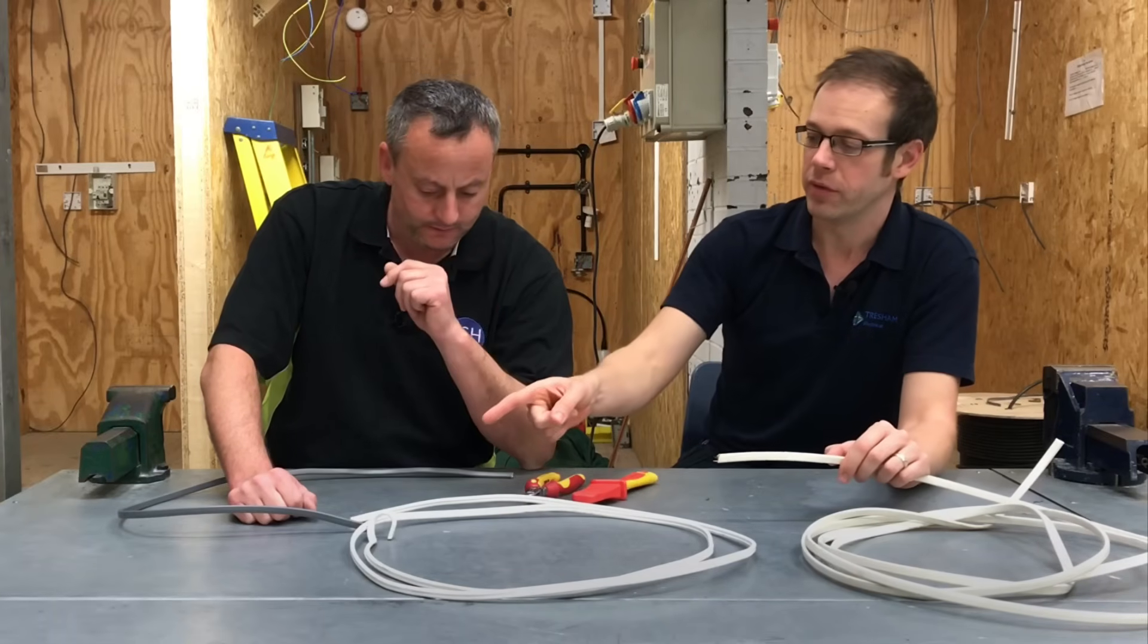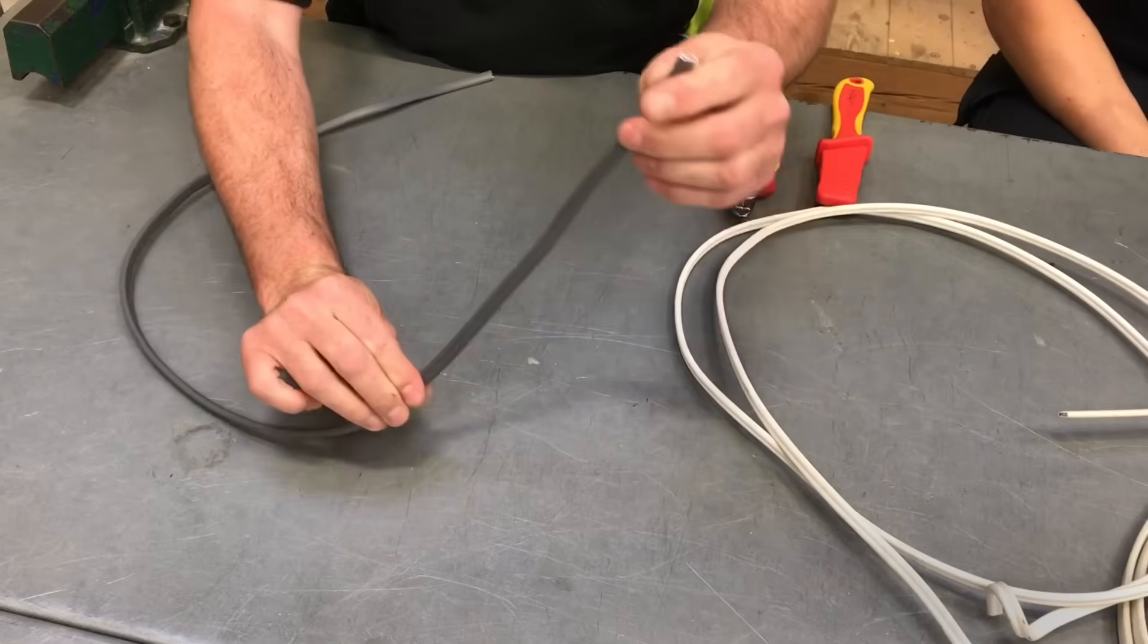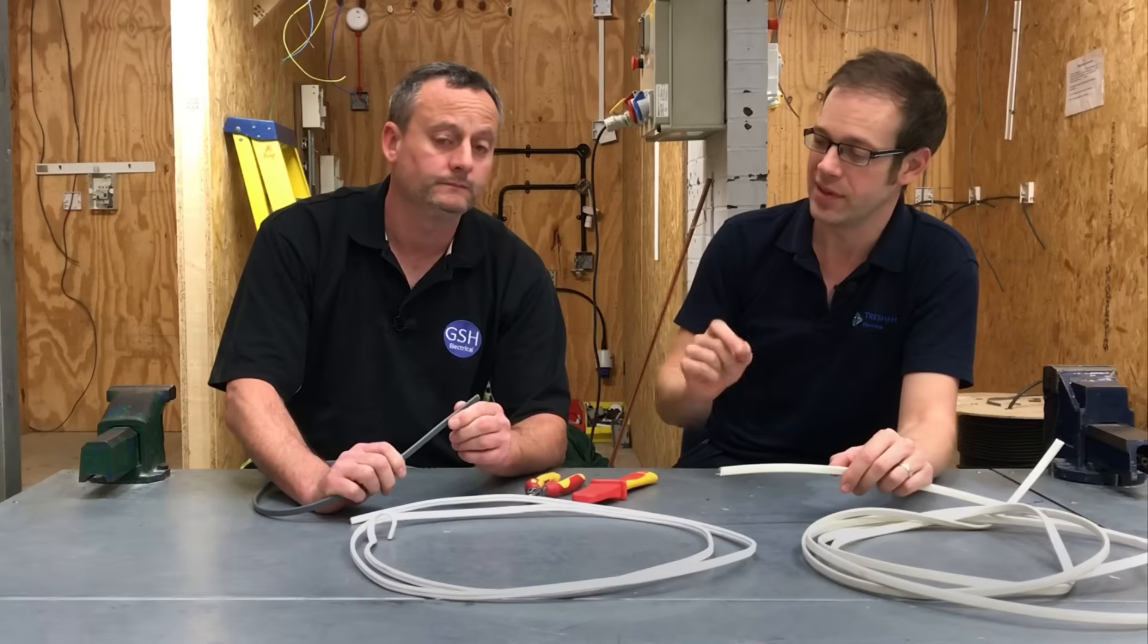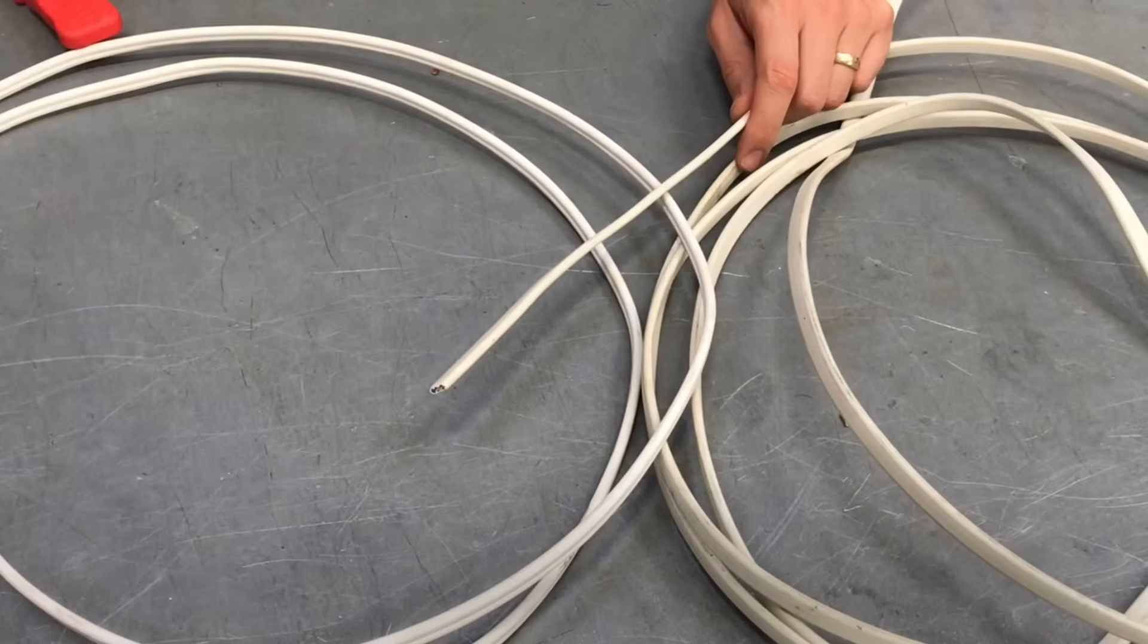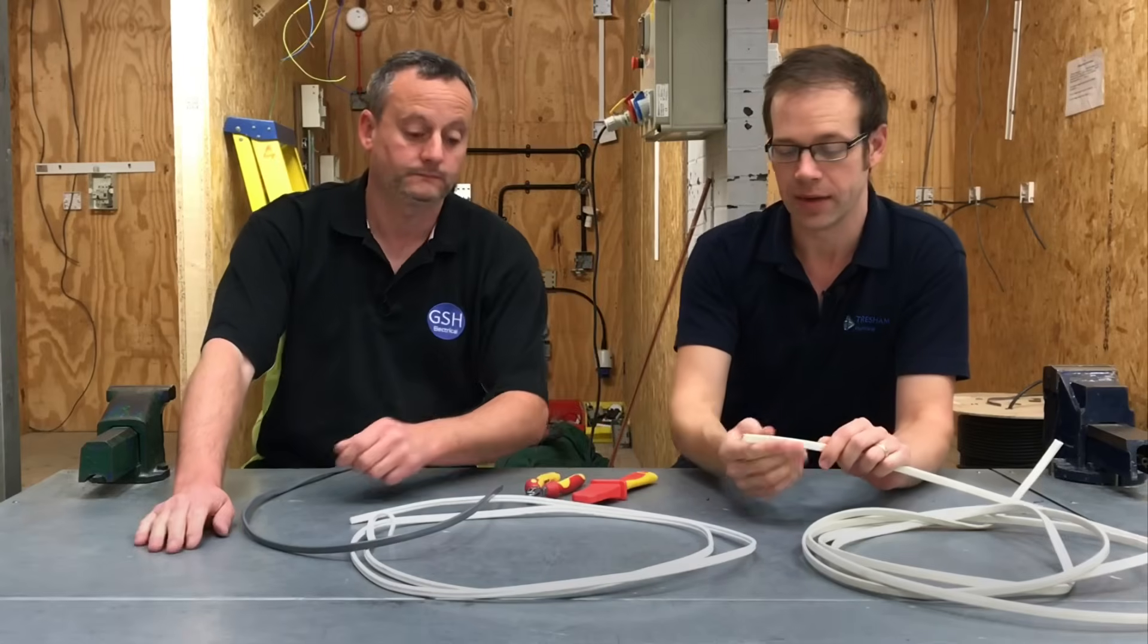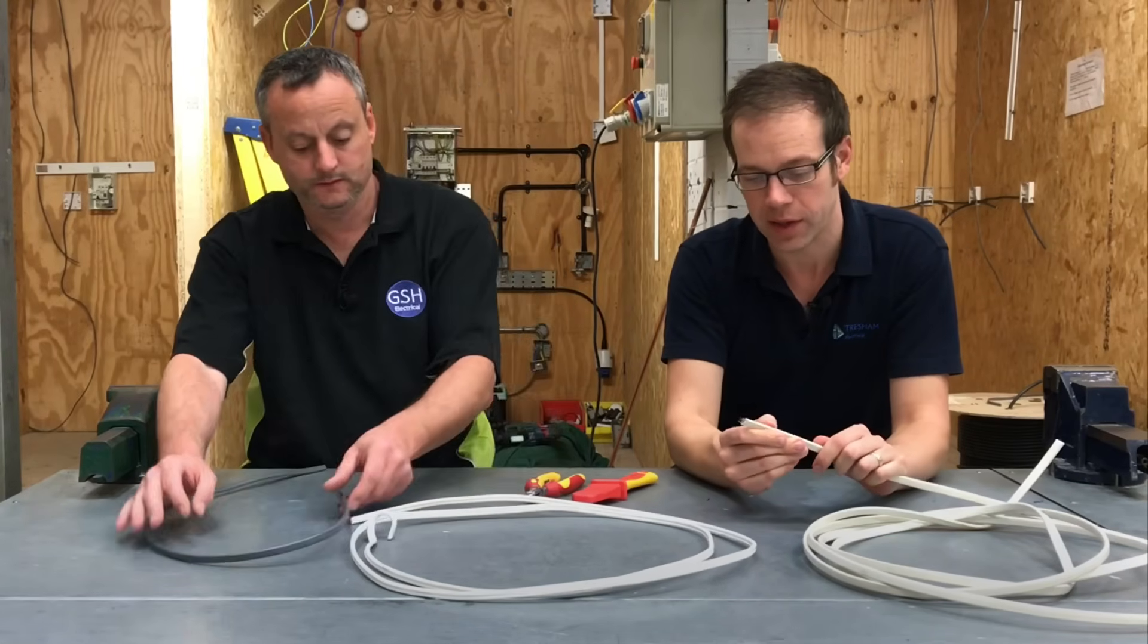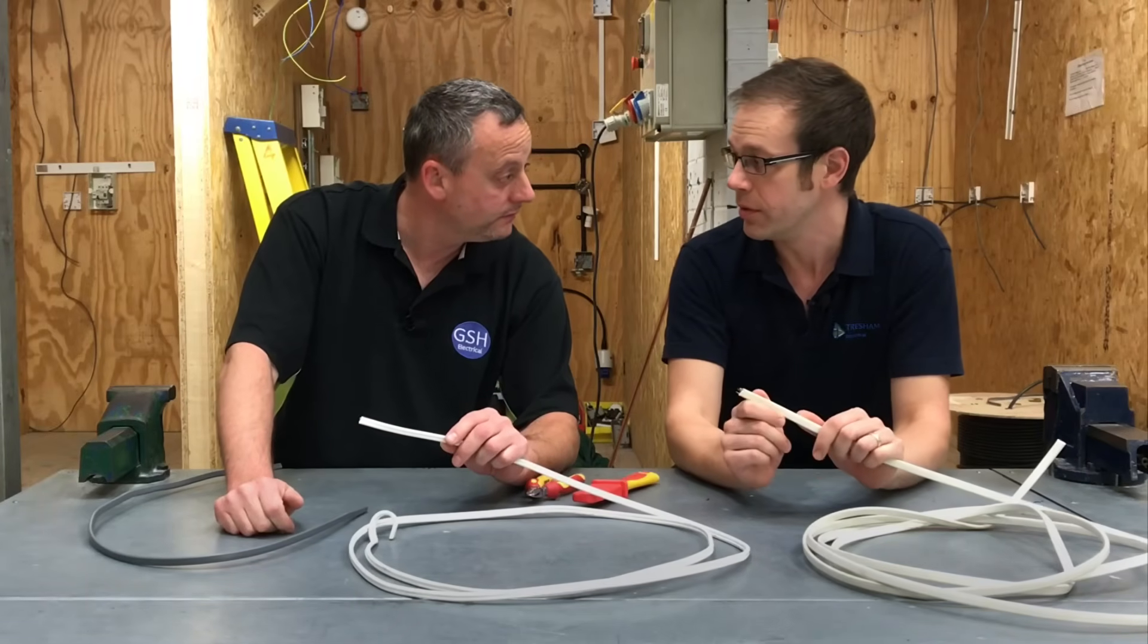The grey cable that you've got in front of you is insulated and sheathed with PVC, which we're quite familiar with. And the designation for that type of cable is 6242YH for harmonised cable. Whereas what we've got here is 6242B cable, and the last letter indicates the material that is acting as the insulation and or the sheath. So this is sheathed with some kind of low smoke and zero halogen material.